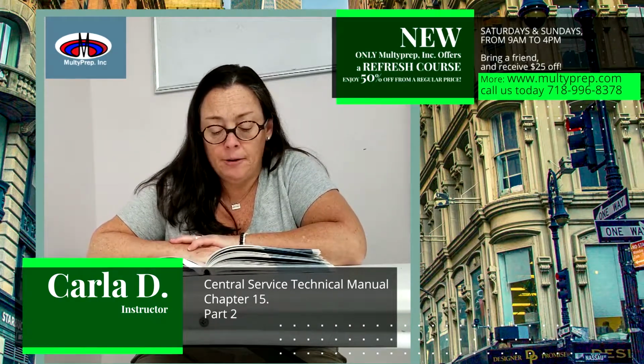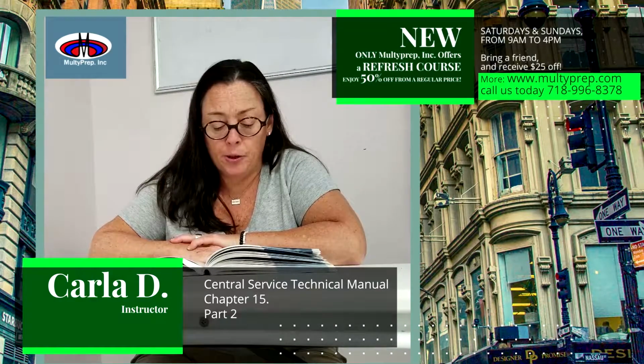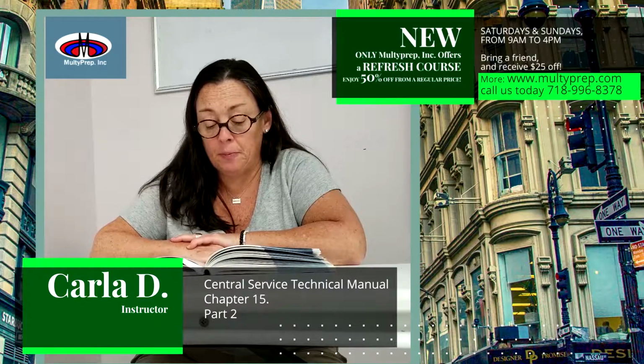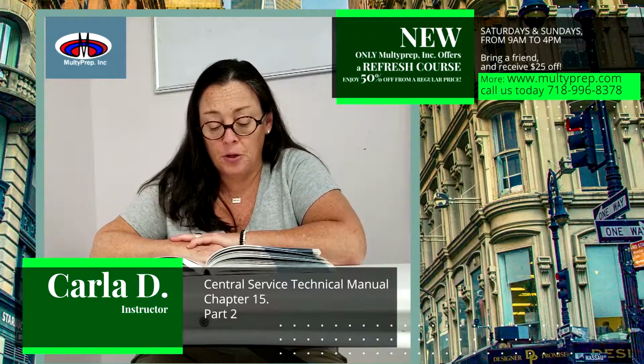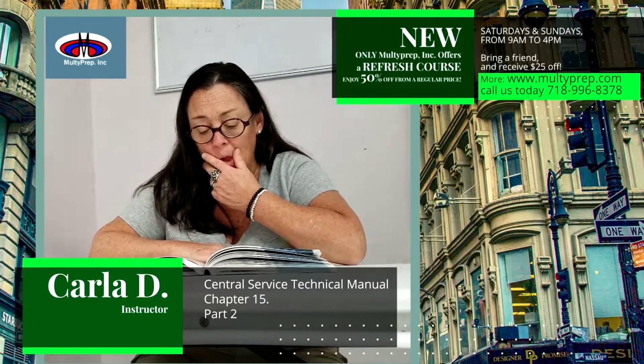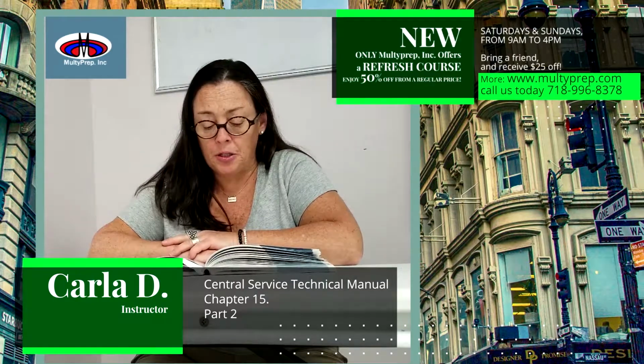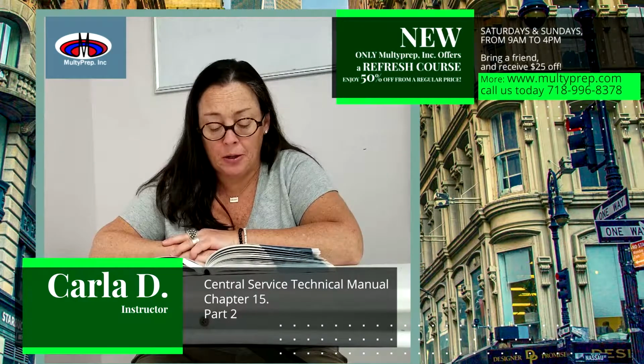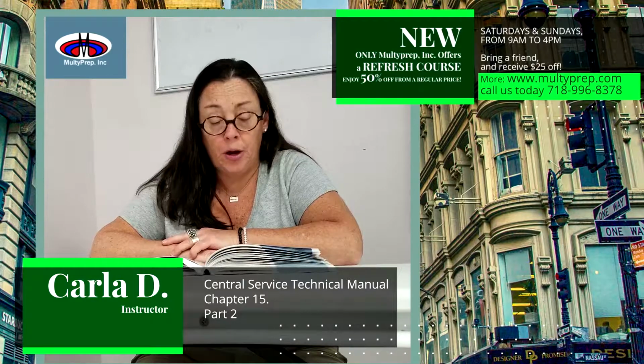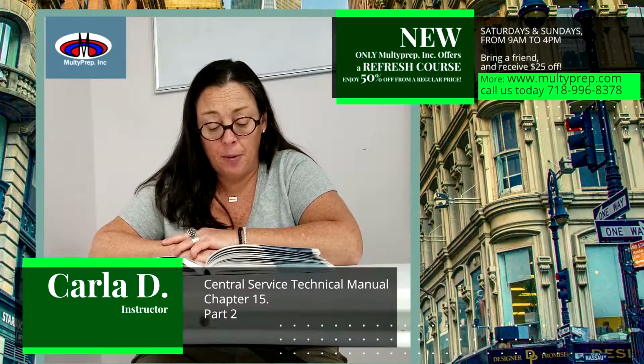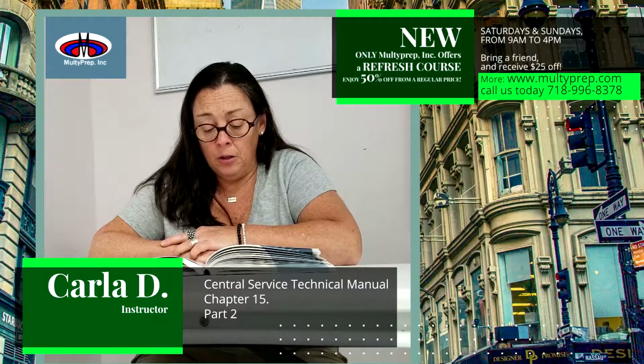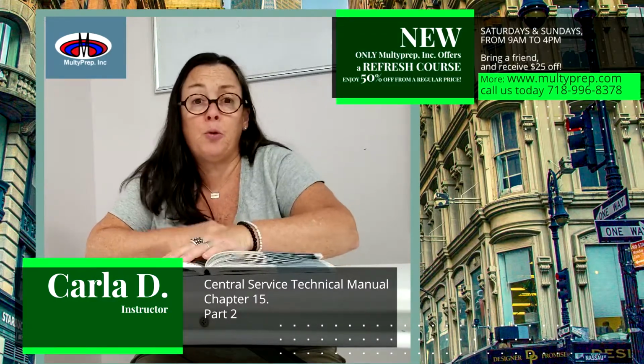Efficacy. Hydrogen peroxide gas plasma using a hydrogen peroxide solution ranging from 59% to 95% for the sterilization cycle is proven effective at killing microorganisms. Laboratory tests have demonstrated that the systems destroy a broad spectrum of microorganisms, including gram-negative and gram-positive vegetative bacteria and mycobacteria, yeasts, fungi, lipophilic viruses, hydrophilic viruses, and highly resistant aerobic and anaerobic bacterial spores.